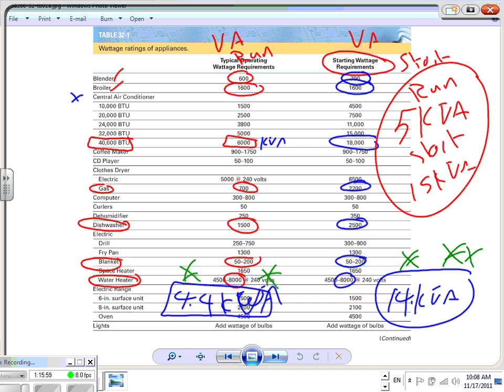How can I control the start current, guys? You can reduce this number by doing a very simple thing: starting things in sequence instead of starting everything at the same time. So add them all up like we did, because they're all going to start at the same time. What if I make a control system that will start them in sequence? The largest load first, wait 10 seconds until it's stable, then the second load, the third load, the fourth load. If you do it this way, you will reduce the starting capability required of the motor.